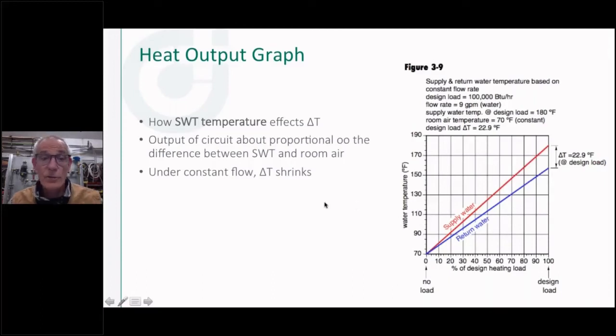You would see that it would shrink as we get closer and closer to the load. Now, what we can do nowadays, which makes this even nicer, is we can put a boiler in there that can modulate with that load also, so we don't have to have a fixed temperature supply, and that's pretty nice. That's a good way to modulate the temperature to a load that changes.